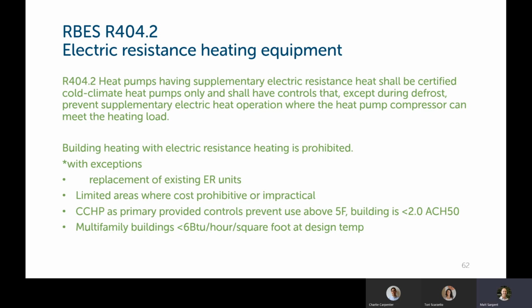So there's also a stipulation around electric resistance heating equipment. So heat pumps having supplementary electric resistance heat, so that's not the integrated electric resistance heat we saw before, shall be certified cold climate heat pumps and shall have controls that, except during defrost, prevent electric heat from coming on when the heat pump can meet the load. So building heating with electric resistance heat is prohibited, and there are some exceptions. So we can replace existing electric resistance units. So in limited areas where it's cost prohibitive or impractical, and these are laid out as sometimes stairwells, bathrooms, things like that.